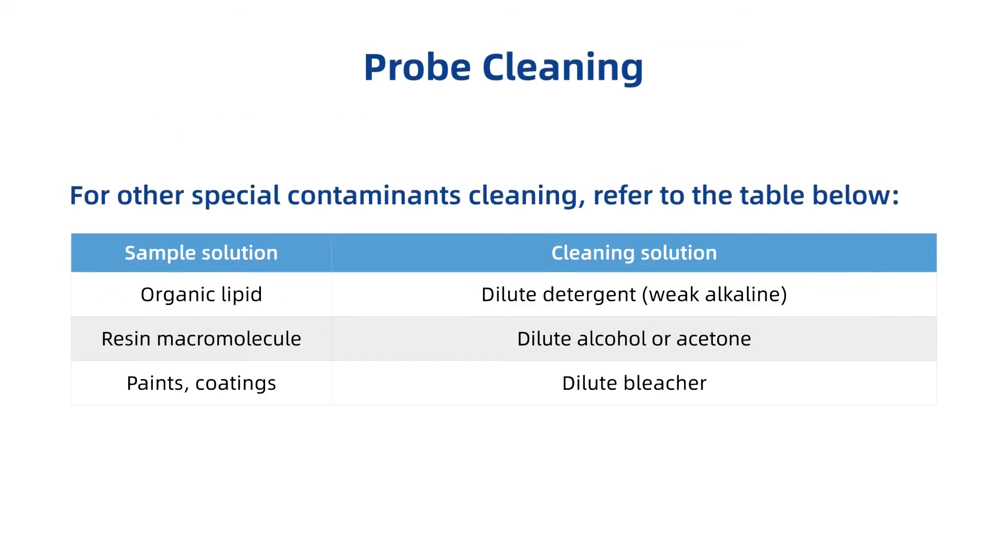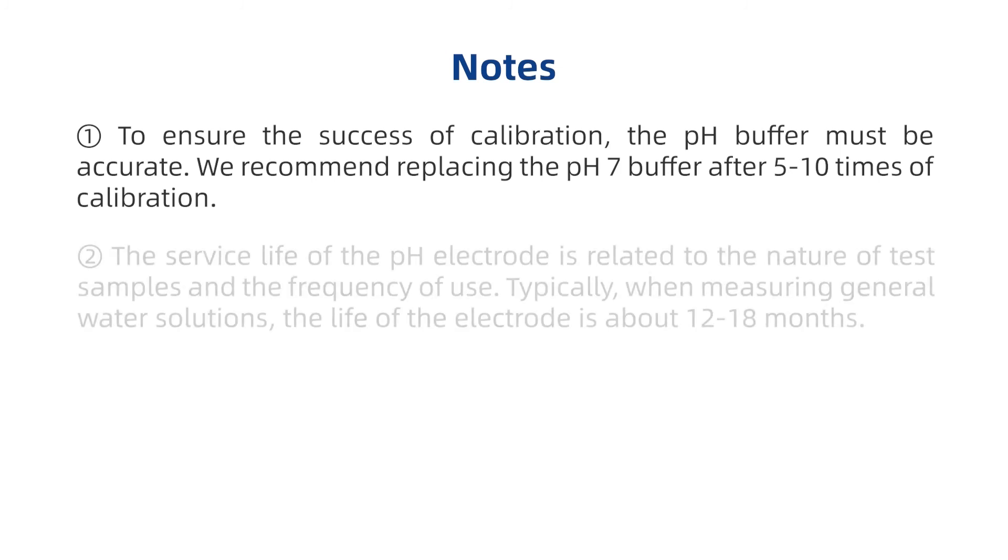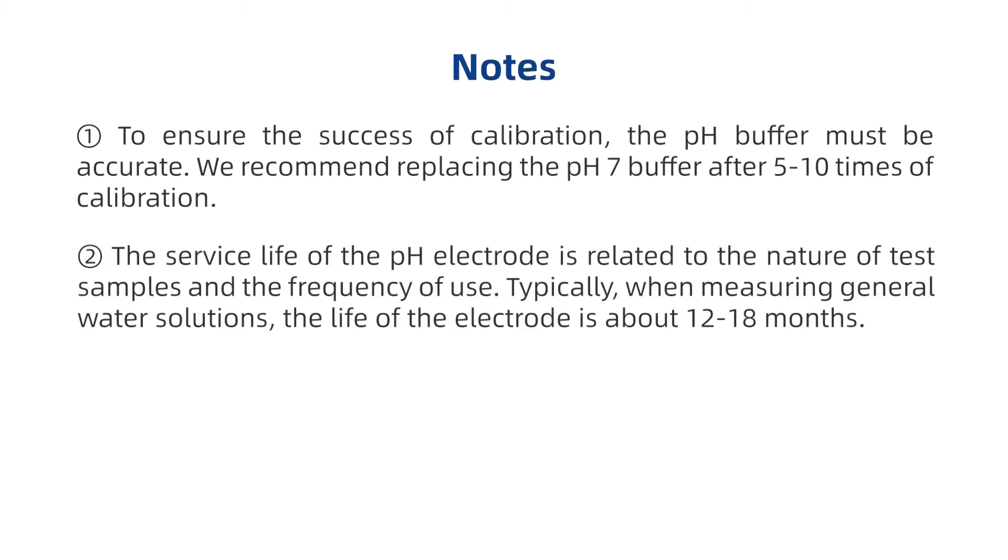For other special contaminants cleaning, refer to the table below. To ensure the success of calibration, the pH buffer must be accurate. We recommend replacing the pH 7 buffer after 5 to 10 times of calibration. The service life of the pH electrode is related to the nature of test samples and the frequency of use. Typically, when measuring general water solutions, the life of the electrode is about 12 to 18 months.